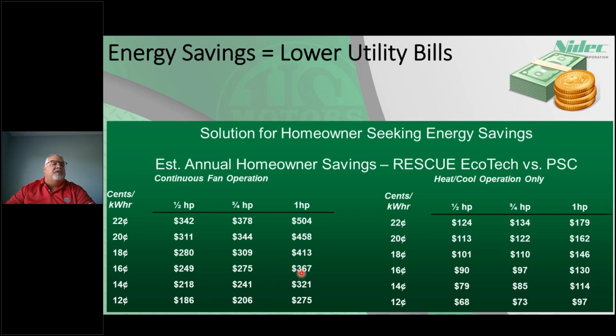So just to give you an idea of the homeowner savings, the customers that benefit the most are ones using their continuous fan. A lot of people don't use continuous fan because it takes so much energy. But at 600 RPM, this motor draws less than 90 watts, or at 90 watts or below basically is what I've seen. At 18 cents a kilowatt hour, a half horsepower motor is going to save $280 a year.